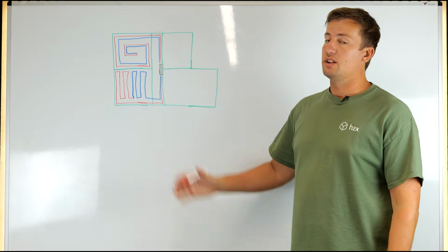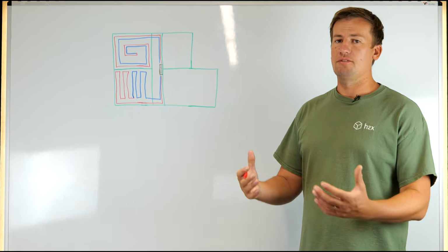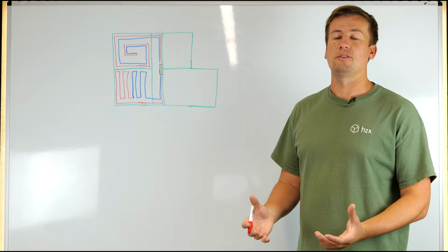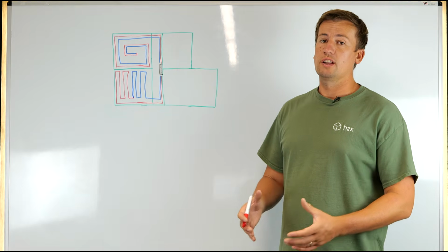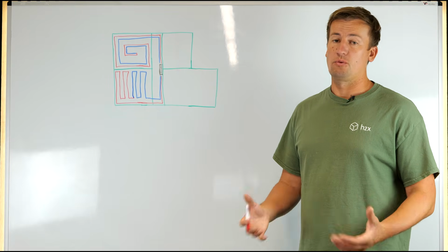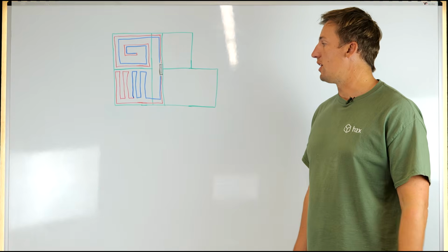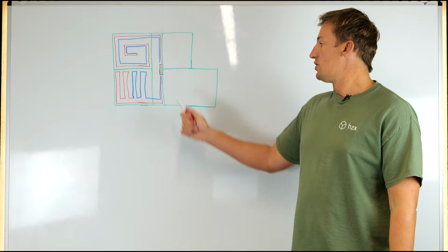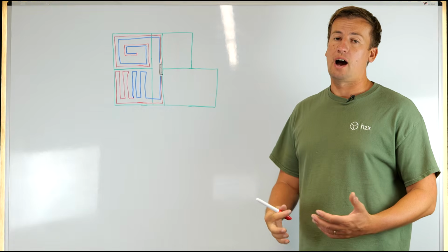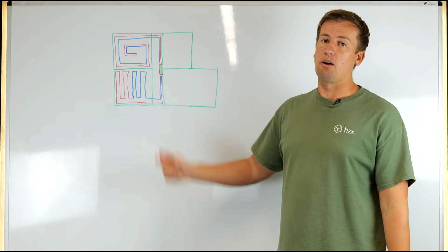And usually this is a really small room, so if you've got 5 different sets of transit pipes coming out of a manifold, it can get really hot in that room, which can be really uncomfortable and cause system failures for the floor. So you want to insulate it so that doesn't happen, and yes, you save the heat output for the area.